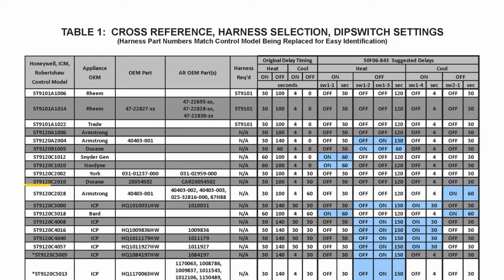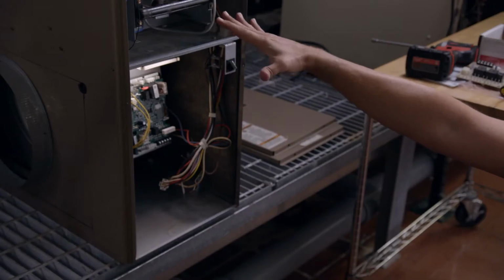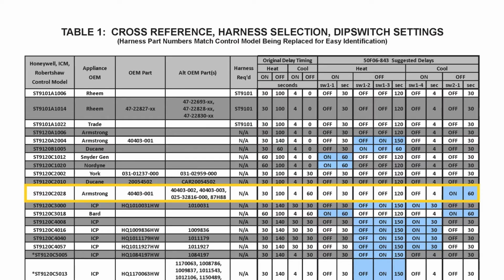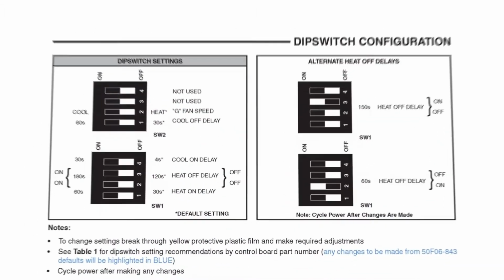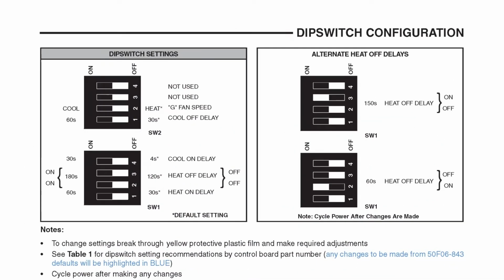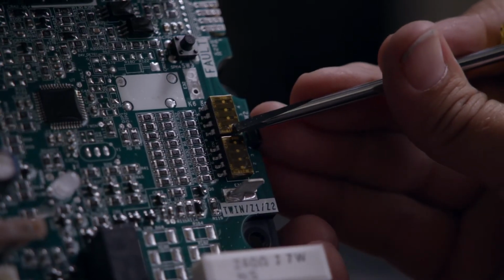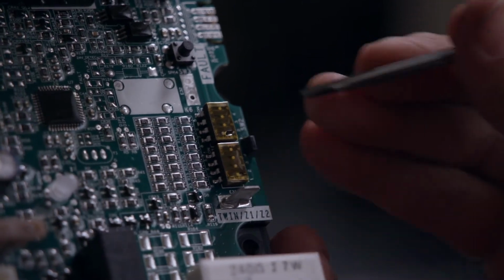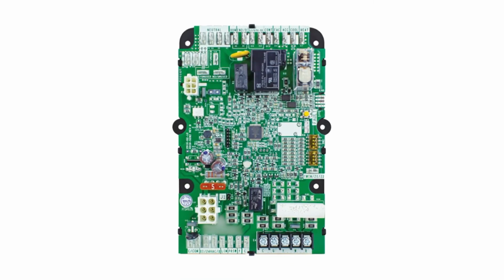Check the cross-reference, harness selection, and dip switch settings table in the instructions. For this model, no harness is required. Any changes to the default dip switch settings will be highlighted in blue. For this model, changing the cool-off delay is suggested. Refer to the table for proper setting instructions. SW2 switch 1 can be moved to the on position by pushing through the yellow plastic film to achieve a 60-second cool-off delay. The control may need to be mounted in different positions.